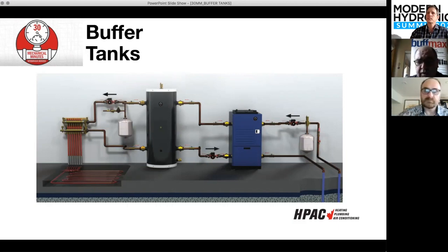Yeah, because again, you want to take advantage of the COP that you're getting out of your heat pump or out of your geothermal, and you want to be able to utilize that energy that it's making later on or as it's needed. And because it's a lower temperature, you want to store as much of it so that you could take advantage. And again, as Steve said, the runtime of your heat pump and your geothermal is reduced, and it takes advantage of when it's getting that cold return, so that it's giving you that high COP from the unit.